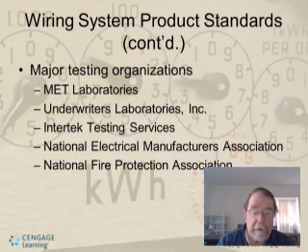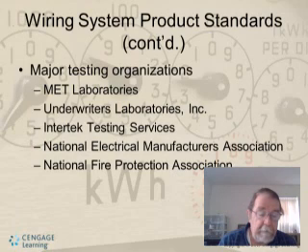Underwriters Laboratories. Prior to the formation of NRTL in '89, electrical product standards were primarily written by Underwriters Laboratories. The good old UL symbol used to be on everything. They performed certification and testing, and standards written by UL are still widely used. The appearance of the UL logo on a label indicates that the product complies with the UL standard. It does not necessarily mean that UL did the product testing. It just means that it met their standard.